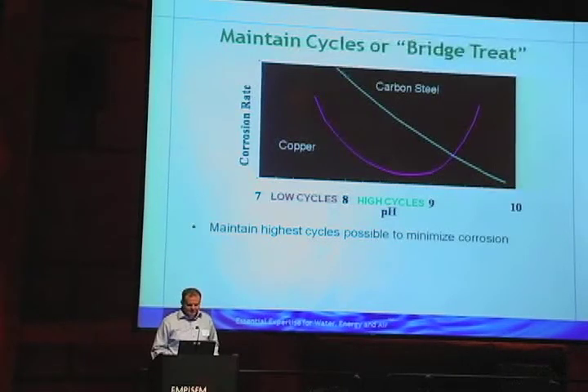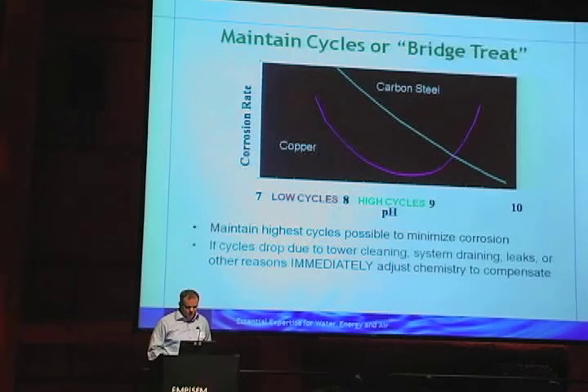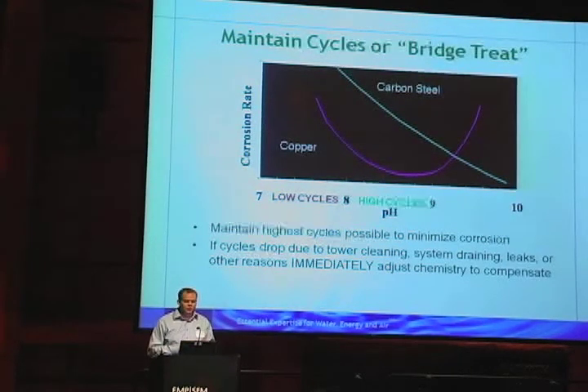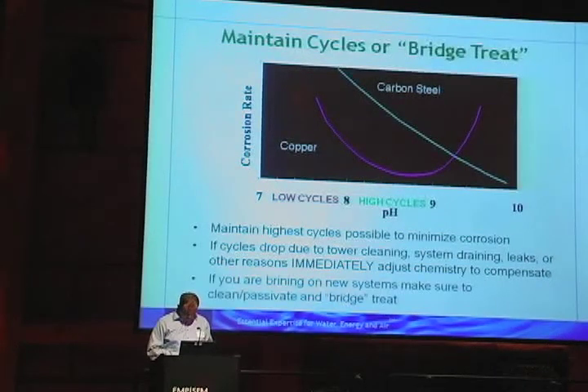So maintain the highest cycles possible without forming scale, and that'll help you minimize that corrosion. If the cycles drop, do something immediately. Don't say, oh, you know, the conductivity dropped to a couple hundred. Let's figure out what we should do. You should have a plan in place. If the conductivity is going to drop, what should you do to fix it? I think I have this on here too.